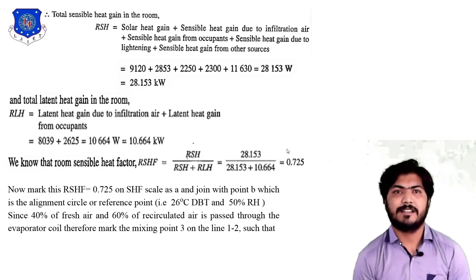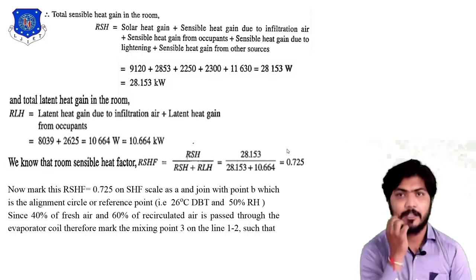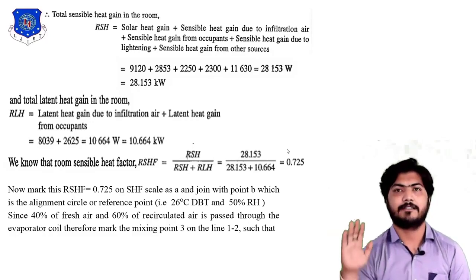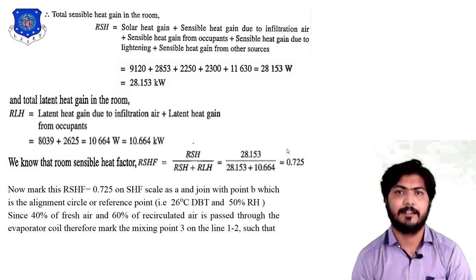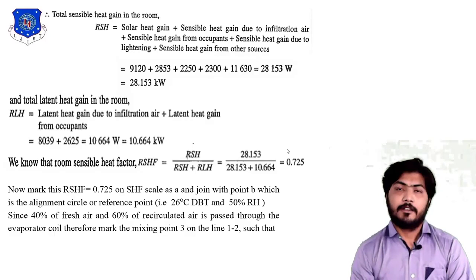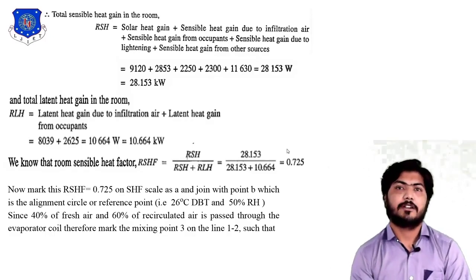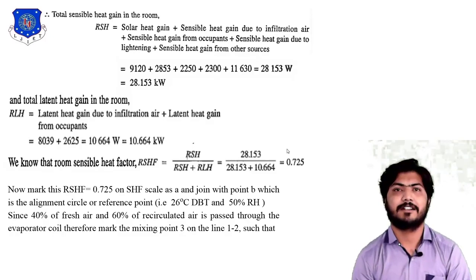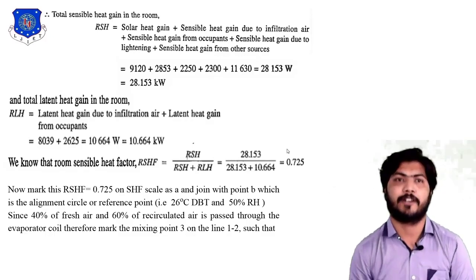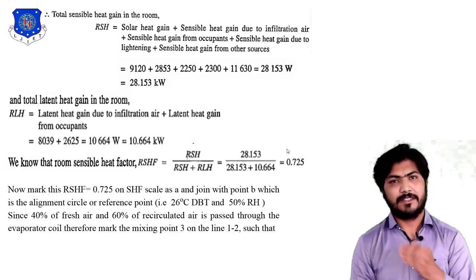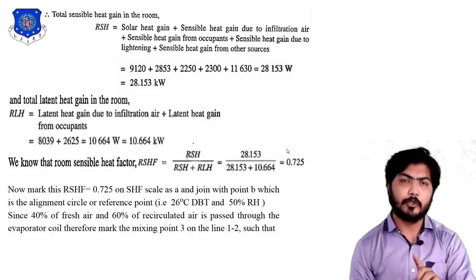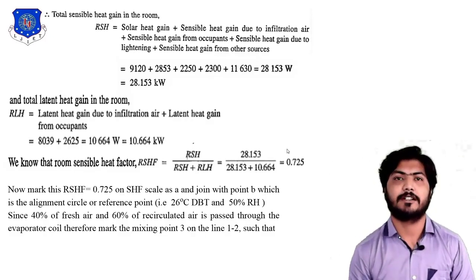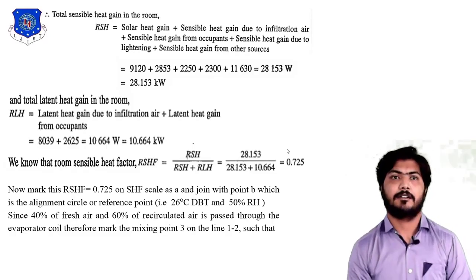This RSHF of 0.725 is marked on the psychrometric chart on the sensible heat factor scale, which is a vertical line on the left-hand side coordinates of the chart. From the marked point 0.725, a line is drawn to the reference point, which is the alignment circle at 26 degree DBT and 50% relative humidity — that is the reference point for thermal comfort. Joining these two points gives the room sensible heat factor line. From this line, a parallel line is drawn from point 2 up to the saturation curve.